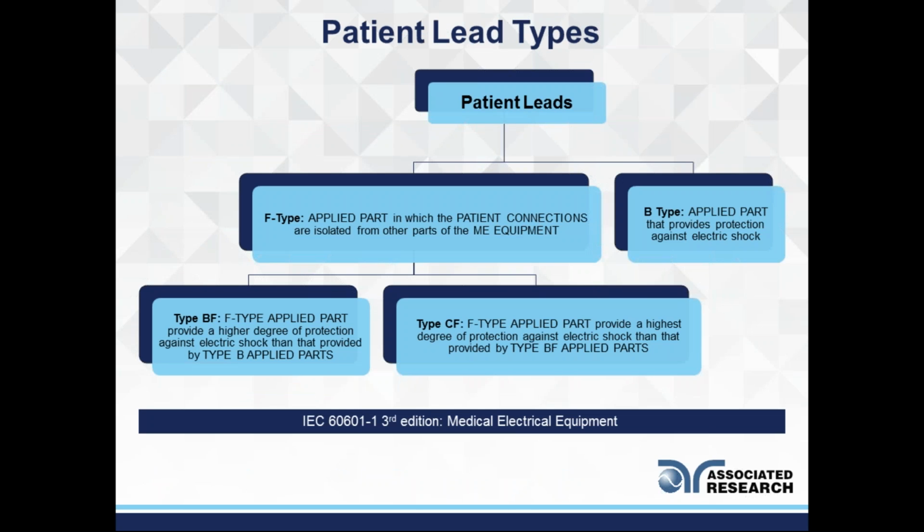So patient lead types. You guys are probably familiar with these terms, and let's discuss some in a little bit of detail. So B-type. To qualify for B-type, it's probably the least stringent as to what you have to pass. Now, B-type is an applied part that provides protection against electrical shock.